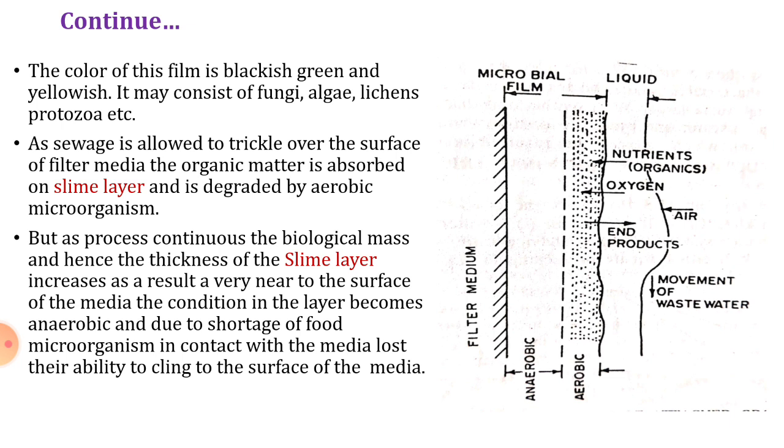As the sewage is allowed to trickle over the surface of the filter media, the organic matter is absorbed on the slime layer and is degraded by the aerobic microorganisms.